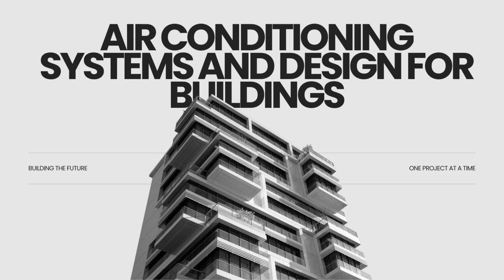Those are really helpful practical tips that immediately make sense from a physics perspective. Okay, now let's talk about sizing. How do we actually figure out what size of unitary air conditioning unit we need for a given space? The source provides some really useful shorthand computations that designers use for preliminary estimates, right? Yes, these are fantastic for quick preliminary calculations. They help designers get a ballpark figure before diving into more complex, detailed load calculations, which consider things like window area, insulation, occupancy, lighting loads, etc. The source gives us two simple rules of thumb for unitary air conditioning cooling load computations.